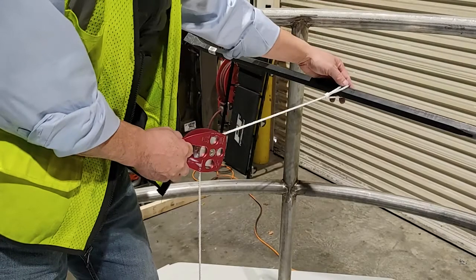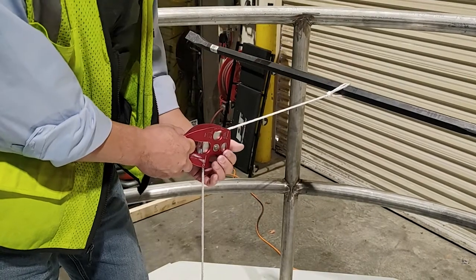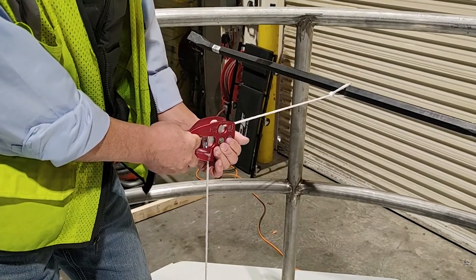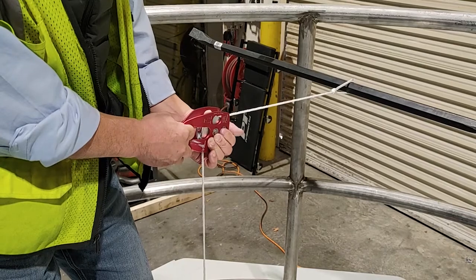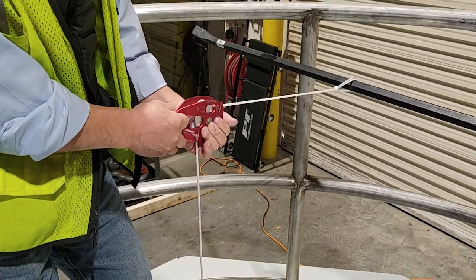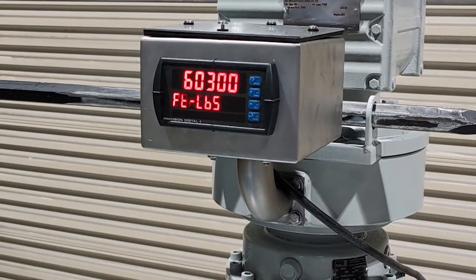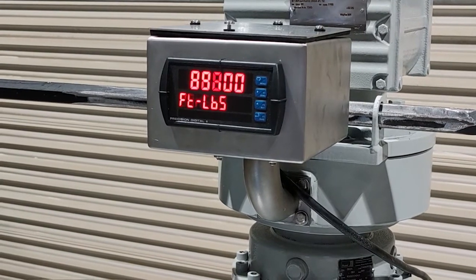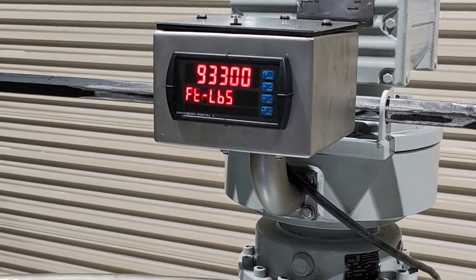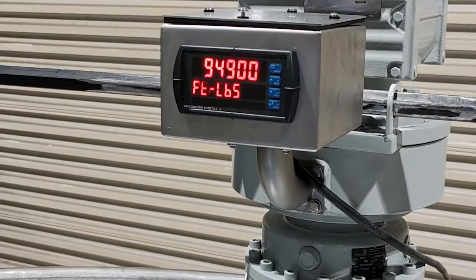It is important to test the calibration of the indicator to make sure the procedure was done correctly. Simply reapply the calibration torque by pulling back on the pulley to lift the weight. If the display shows the value you entered, then the calibration is correct. Otherwise, you will need to repeat the procedure.